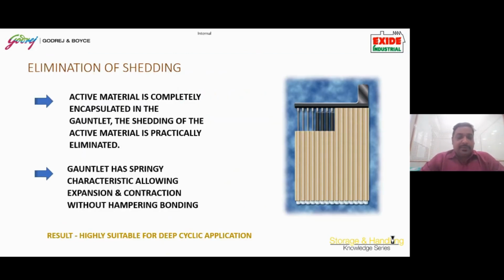As I explained, in cyclic applications this eliminates shedding, which is the primary cause of capacity loss in batteries towards the end of their service life. The active material is completely encapsulated in the gauntlet, so shedding of the active material is practically eliminated. This also has a springy characteristic, allowing expansion and contraction without hampering the bonding, so the active material bonding is not broken, due to the tensile strength and material properties of the spines and the gauntlet.